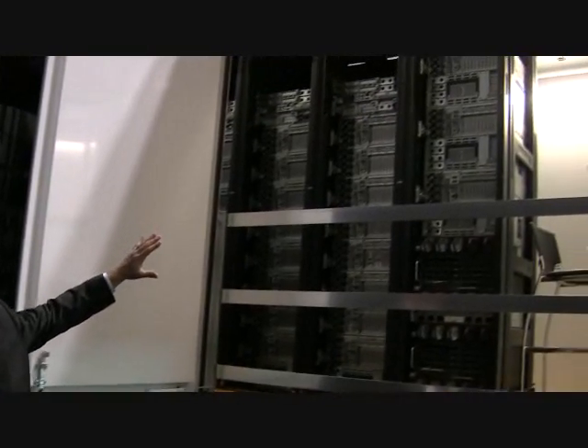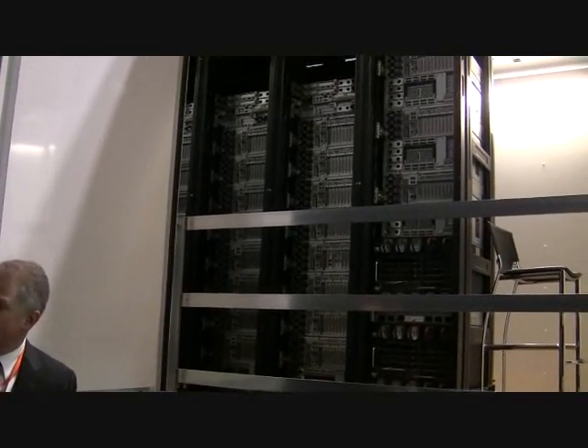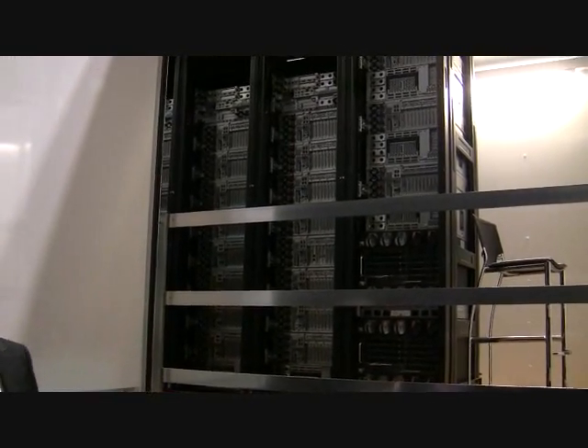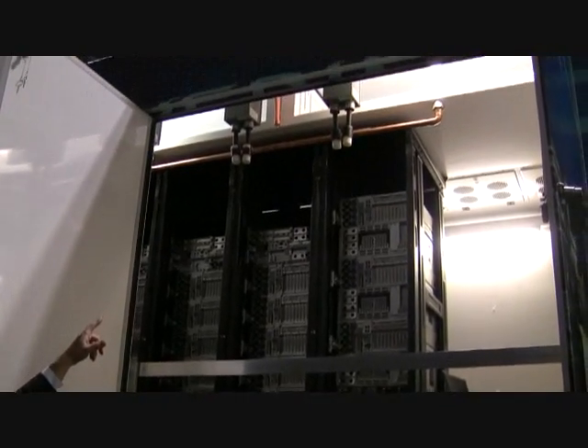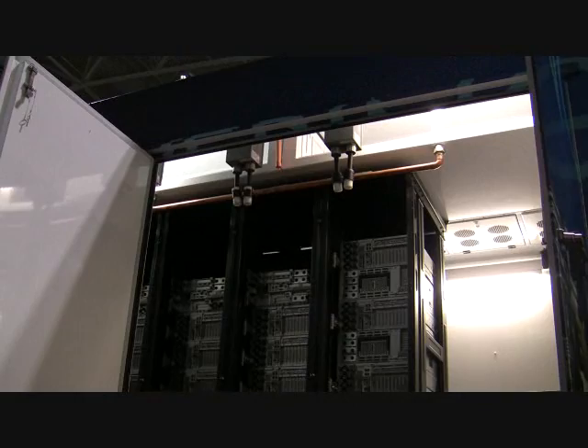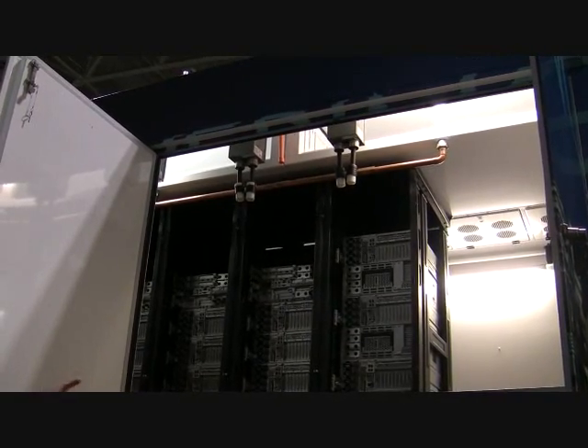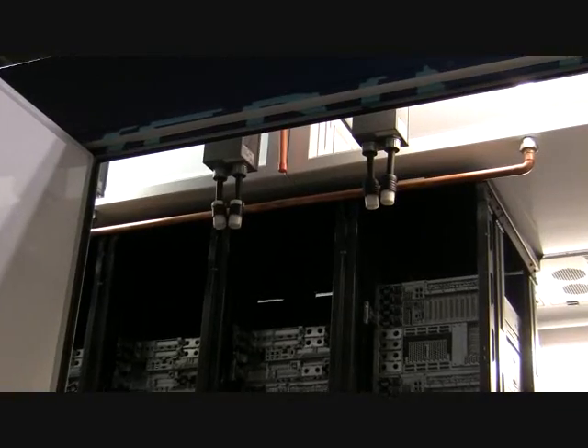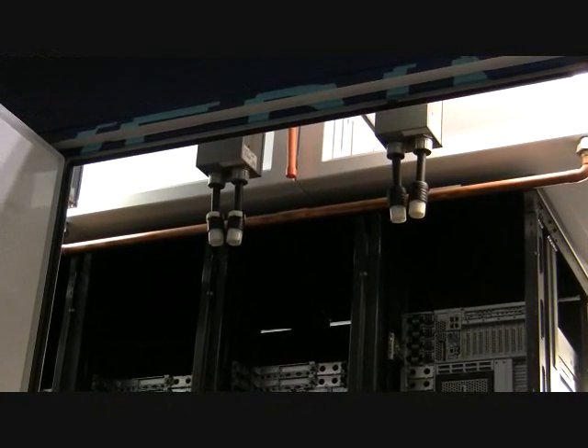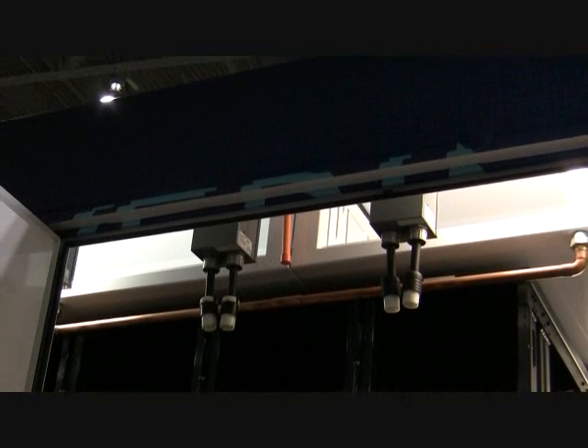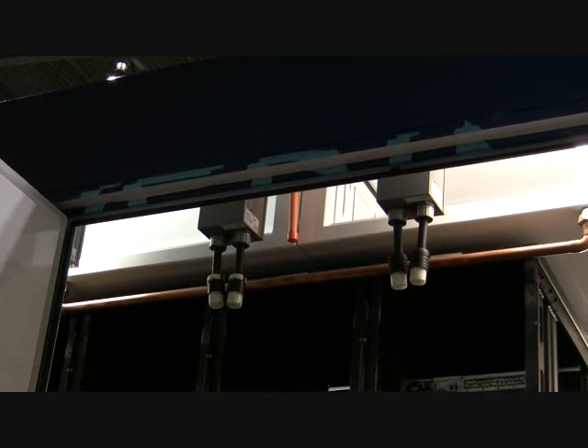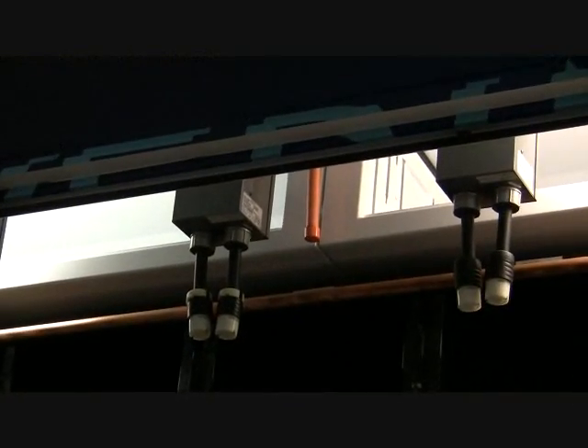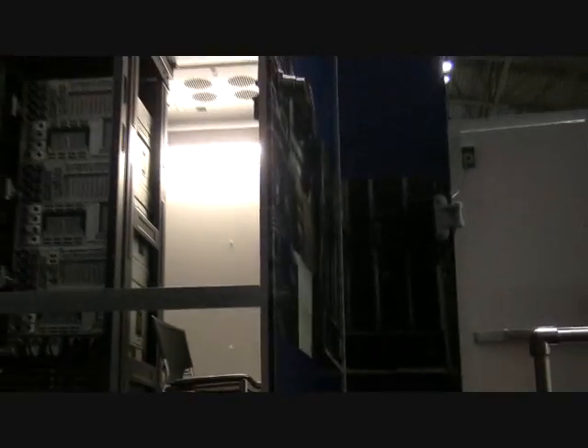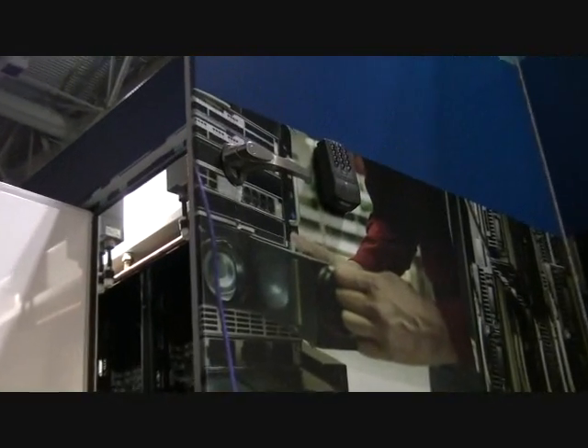Looking at the back here, this is our hot aisle access. Normally this would be on the ground, or if you had them stacked two high, you'd have a scaffolding system to access it. We have redundant power dongles up there that provide redundant power to each of the racks. You would also see that copper piping, which is simply a condensate drain capability from the exchangers, and then there's fire suppression. Complete fire detection and fire suppression systems are included in each of the pods, as well as security. Here we have cipher pad access to all the doors throughout the pod, so complete integrated security as well.